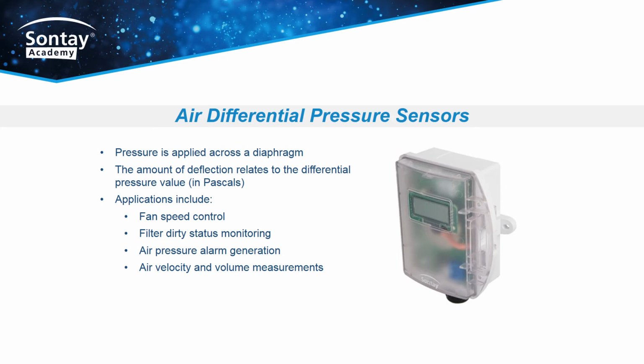Air differential pressure sensors can be used to sense static pressure in an air duct and control fan speed to maintain a constant pressure. This is especially important for variable air volume systems, which require a constant static pressure in the supply duct. Under partial load conditions, the VAVs will shut down, causing an increase in duct pressure, which can be used to slow the fan down.